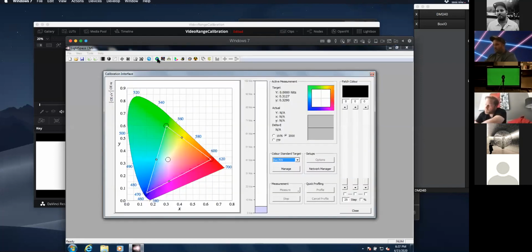So I'll start here. There's two ways to do Lightspace cals. There's the calibration interface and there's display characterization. Calibration interface was originally more for evaluating displays, kind of doing validations. Display characterization is what traditionally was done to do volumetric characterizations and then build LUTs from that. What's happened though is that with a lot of linear displays, you really don't need to do a lot of measurements. So you can use these really short, quick profiles as they're called, and you can actually just build your LUTs from that. So that's the example we're going to have here.